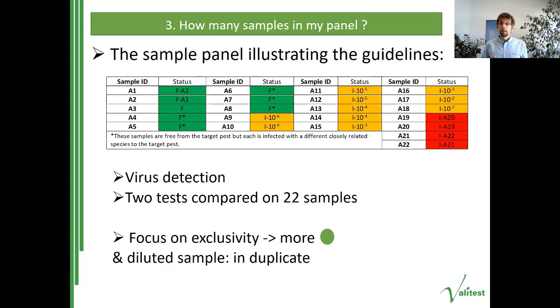The sample panel needs to be adapted depending on the intended use of the test and the most important criteria to evaluate. The sample panel used in these videos to illustrate the guidelines and statistical analysis is one used with the aim of detecting viruses. We compare two tests on 22 samples with a series of participating laboratories. This panel has a focus on exclusivity — many more healthy samples infected by closely related targets — because this was a potential weakness the organizer wanted to evaluate. The diluted samples use five dilution points as recommended, but in duplicates, illustrating the flexibility in panel setting.